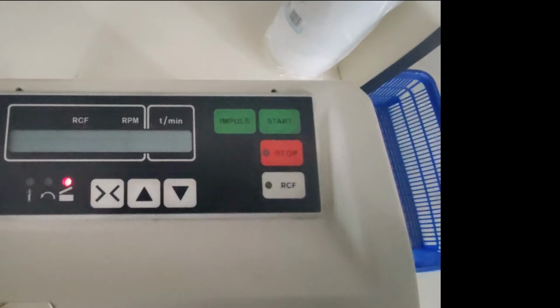Then we have the three indicators, each a symbol with an LED. The first is the balance error - if this LED is lit, the rotor must be loaded evenly. Then there's a rotation indicator - if lit after the start button, it remains lit until the rotor comes to rest, meaning the centrifuge has started spinning.